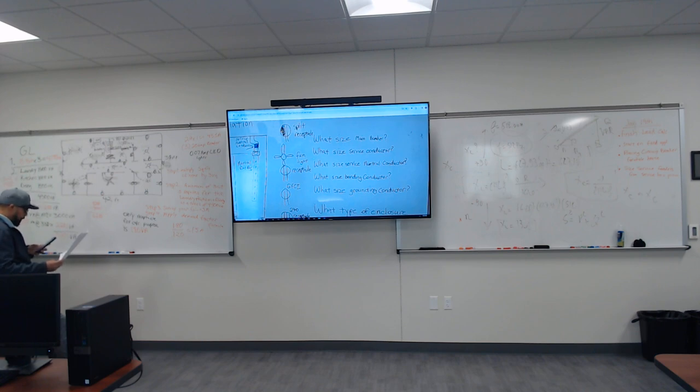If you add all that up, I got 50,223 VA. Now, number nine says conductors are permitted to be sized at 83% of the demand load if it's 240/120 single phase and not greater than 400 ampere. So we don't know how many amps that is, but let's figure it out. In the home, do we have 120 or 240, or both? Both, but the one you want to utilize is the 240. We take that 50,223 VA or watts and divide it by 240. Right now we're under that threshold of 400 amps, so we can use the 83%.